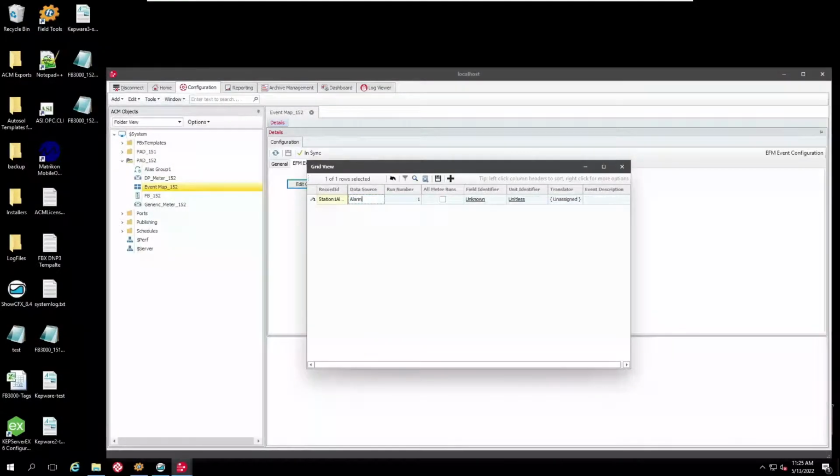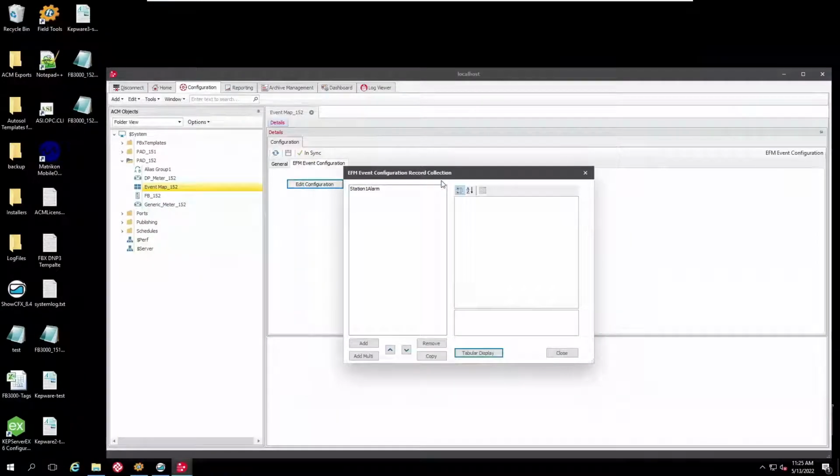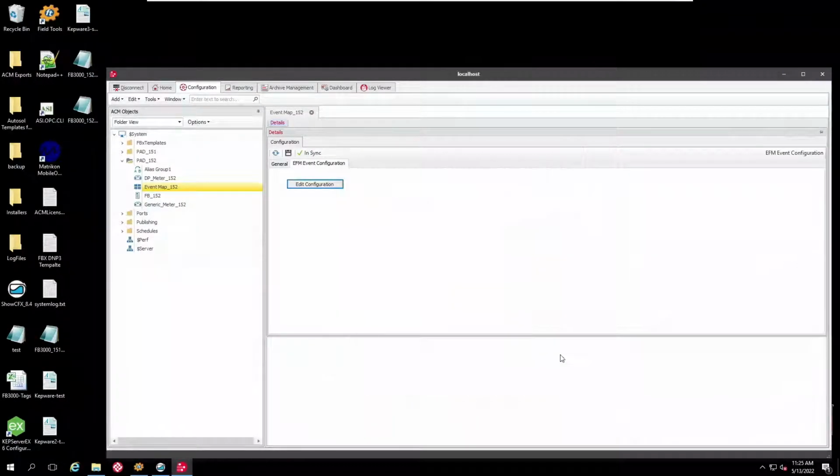And if you recall, this was alarm 1801. So enter the text alarm_1801 and then equals M. This means it will do a match. It will search for that text in the alarm and event history. And we're going to map that to run number 1 as it's the first meter in this RTU. You can actually edit in this form as well. I'm just showing the results.